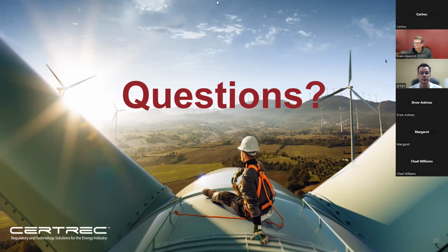Okay, so we got a question. Does your data format comply with any industry standards? Good question. As I mentioned during the discussion today, we have a dual data stream. One is a DNP3 industry protocol directly into third-party SCADA systems, which can be RS-485 twisted pair, or Ethernet, or Wi-Fi, or fiber TCP/IP communication. The data format for the high-resolution waveform captures is in a proprietary format coming out of our device, the smart block. But as soon as that data file hits the WaveIQ server application, the first thing WaveIQ does is convert that data file to industry standard formats. Comtrade is the most common that our customers configure the application for.